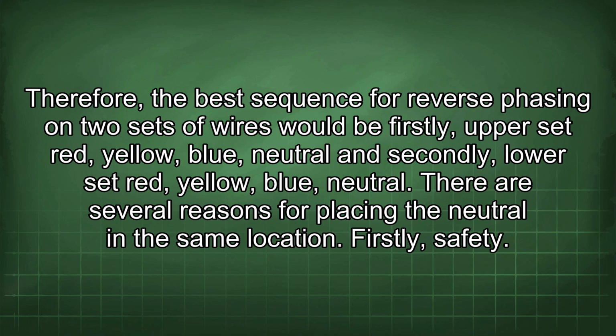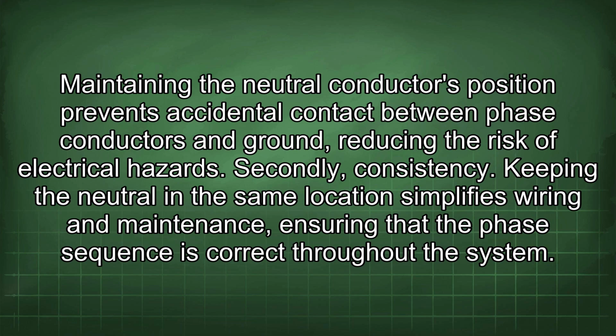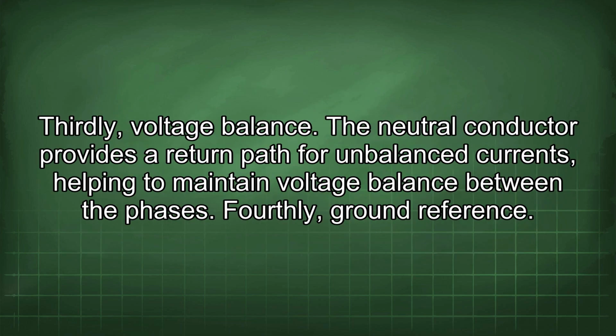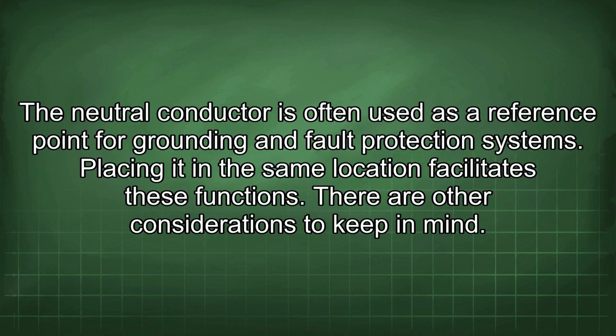There are several reasons for placing the neutral in the same location. Firstly, safety. Maintaining the neutral conductor's position prevents accidental contact between phase conductors and ground, reducing the risk of electrical hazards. Secondly, consistency. Keeping the neutral in the same location simplifies wiring and maintenance, ensuring that the phase sequence is correct throughout the system. Thirdly, voltage balance. The neutral conductor provides a return path for unbalanced currents, helping to maintain voltage balance between the phases. Fourthly, ground reference. The neutral conductor is often used as a reference point for grounding and fault protection systems. Placing it in the same location facilitates these functions.